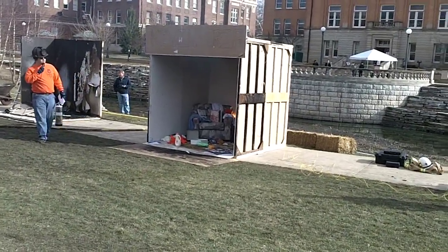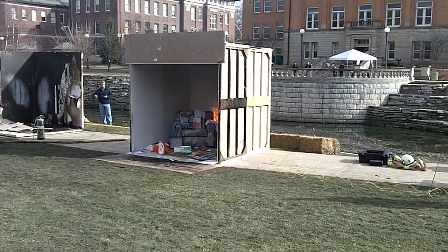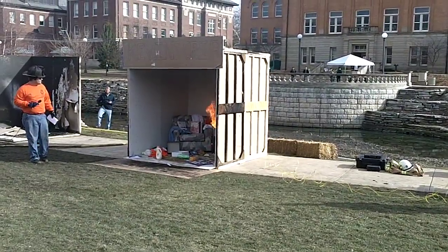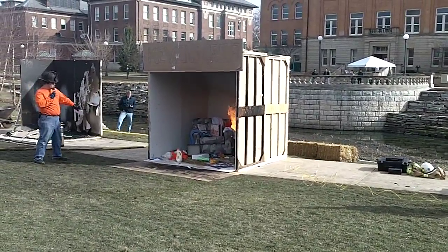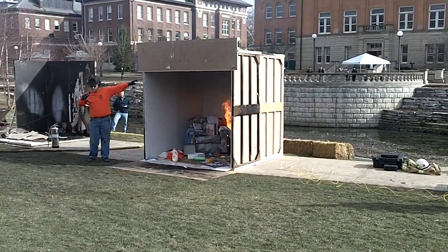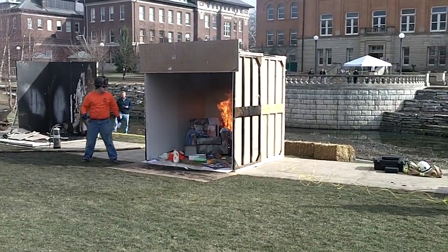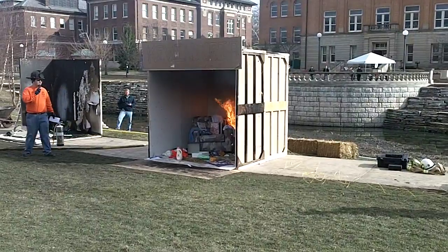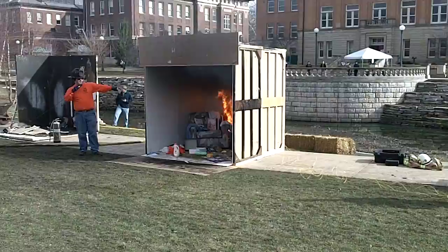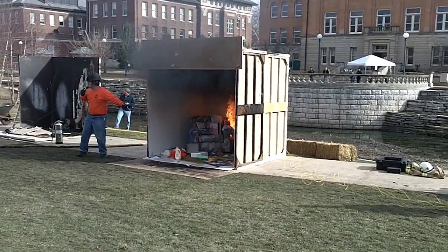The fire is now attacking the recliner. We have 150 at the ceiling. You can start to see the smoke grow from this fire — the layer is at about right here right now. 200 at the ceiling, floor is still at 50 degrees. You can see the black smoke now growing down; the hot layer is making its way down into the cold zone.